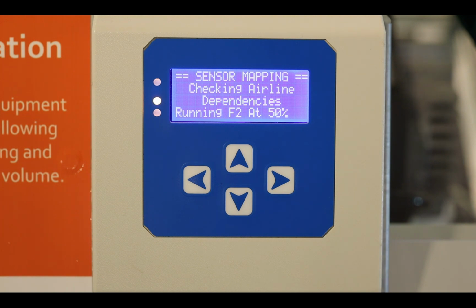On finding fewer sensors than fans, the controller then operates the fans without the pressure transducer connection, one by one, to determine which transducer it is sharing.